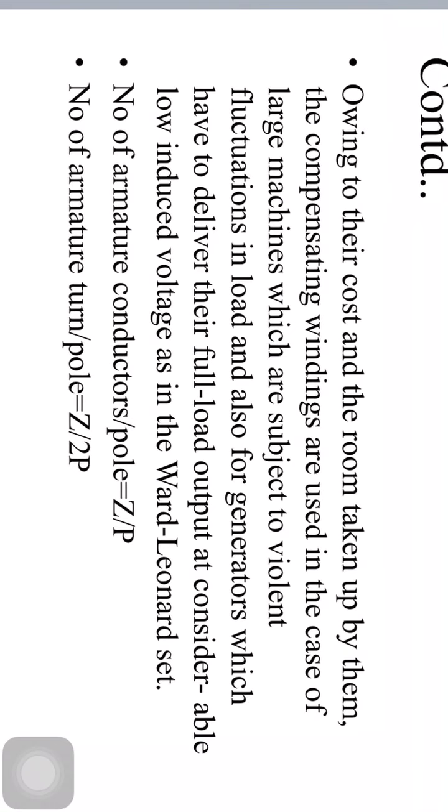And considering the cost and the room taken up by them, compensating windings are used in case of large machines which are subjected to violent fluctuations in load, and also for generators which have to deliver their full load output at a considerably low induced voltage.